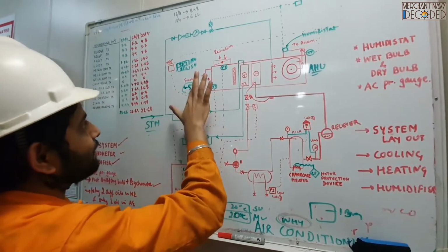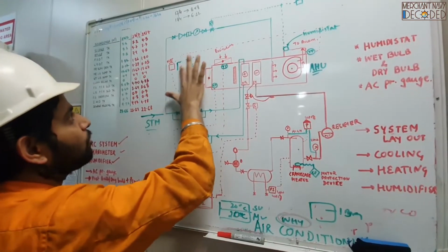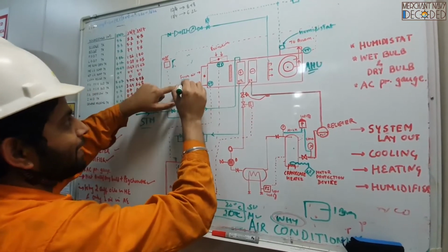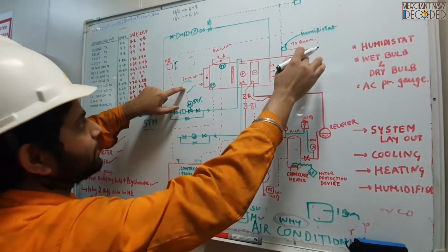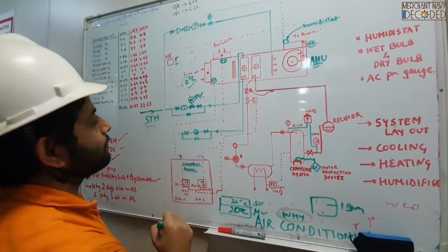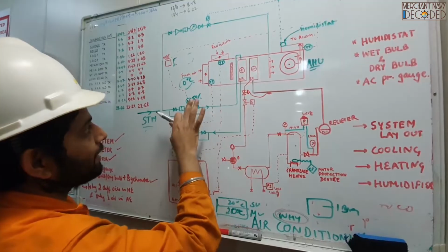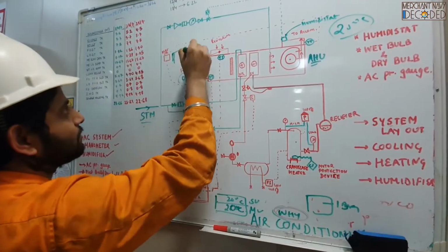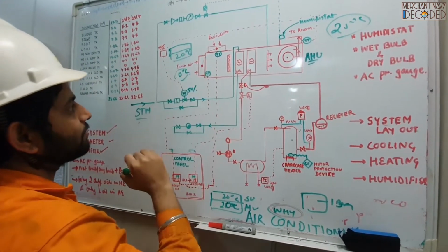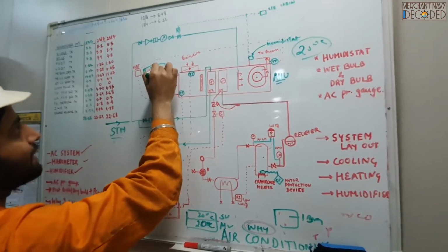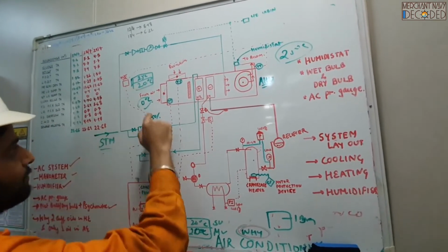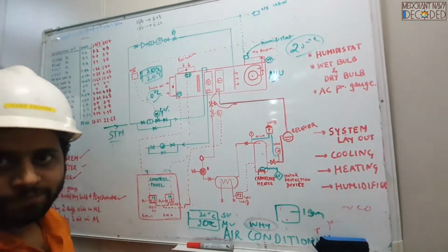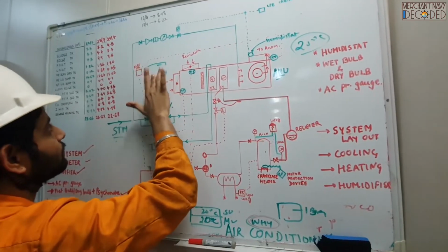Copied? Now after some time we go into a little bit warmer climate. So this valve was open say 50% when the minus 5 degrees centigrade temperature was there, and we wanted 20 degrees over here. Now say the temperature becomes 0 degrees centigrade. That means now 0 degree centigrade air, heated at 50% valve open, is becoming 25 degrees centigrade. But we want 20 degrees because the set value was 20 degrees centigrade. So it says, it is 25 degrees centigrade, shut the valve. So it gives a signal and the valve opens 40% now. And accordingly, again the temperature comes to 20 degrees centigrade. So this is how this controller is working.